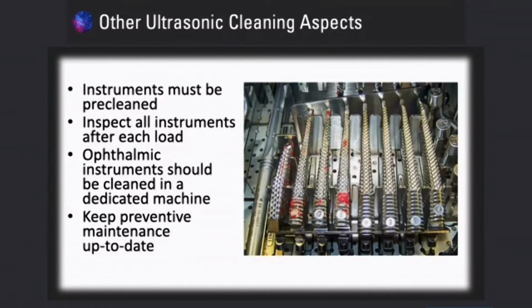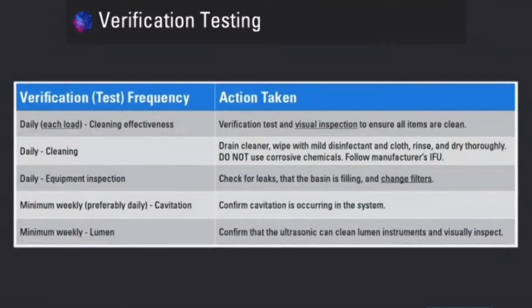And again, like I said earlier, ophthalmic instruments should be cleaned in a dedicated machine. Keep preventive maintenance up to date. So you take care of your machine, we'll take care of you. Plain and simple. So for verification testing daily, for cleaning effectiveness, verification tests should be performed to ensure that all items are clean. Daily cleaning: drain the cleaner, wipe with a mild disinfectant and cloth, and rinse and dry thoroughly. Don't use corrosive chemicals. You don't want to damage your machine. Again, follow the manufacturer's IFUs.